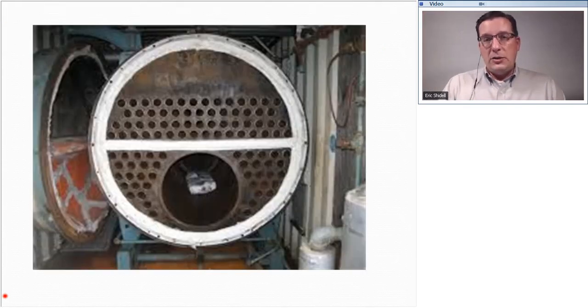Now, shell and tube boilers have doors on the front and on the back. And in this one, we have the back door open. And I want to caution you, if you are new to looking at these kinds of boilers, avoid the temptation to open one and look inside for a couple of reasons. First of all, every one of these doors has a gasket surrounding it. And the gasket is called a rope gasket. It looks just like a rope. And it's made of a material called Kaowool. And Kaowool is the modern replacement for asbestos. It does not burn. It withstands very, very high temperatures. And that's why it's used as the gasket on the fire side of the boiler.